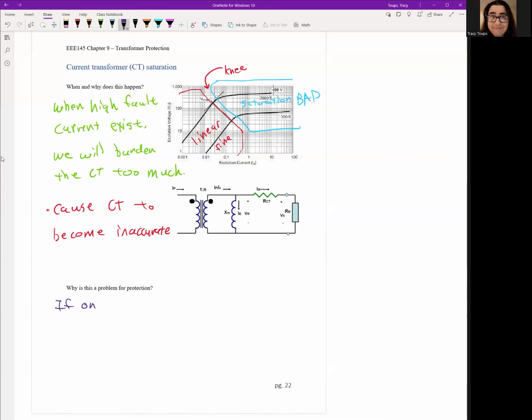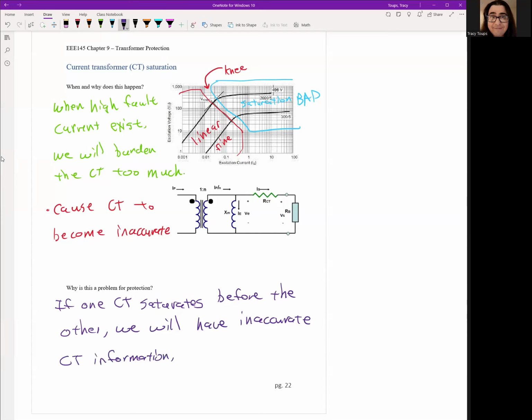If one CT saturates before the other one, which is very common, we will have, number one, inaccurate CT information. And then the 87 relay will probably trip. Okay. So again, it always comes down to this: if we don't feed the 87 relay accurate information from the system, it's going to wig out and trip offline.